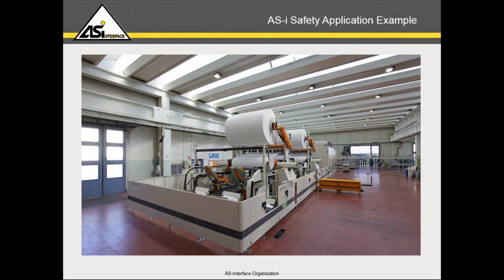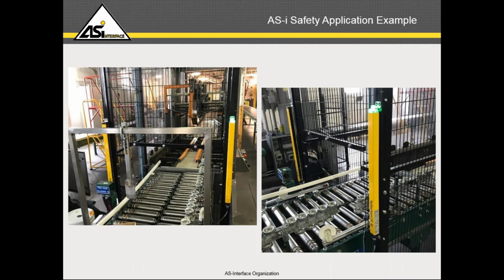So if you look at this machine, wiring all these 48 push buttons and 16 stops and 16 door interlocks with lock and unlock functions, we have a lot of functions in this machinery. Then we look at a smaller machine, where we have an entry-exit area where the box is entering and exiting for taping of that box. So it's a taping machine where we are using two light curtains. One is an entry area to the machine and one is an exit area for the box to enter. So we are using a muting function in this light curtain.